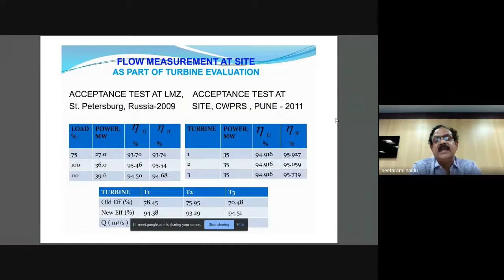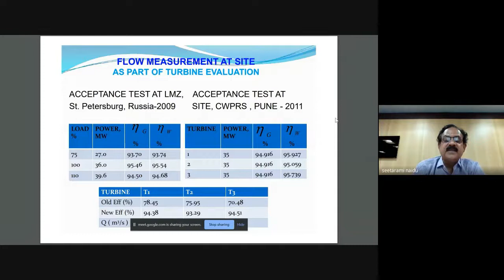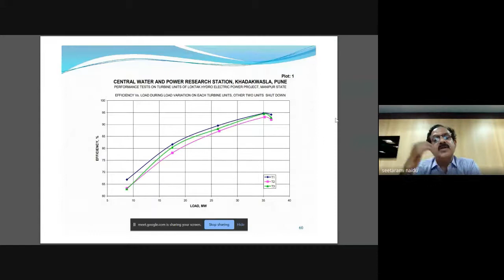In CWPRS we witnessed the acceptance test at site, in 2011 I believe. What they guaranteed is 94.916 for all the units. What we found was an efficiency of 95 odd for all 3. So ultimately, the efficiency has increased from 78 to 94. Just imagine, more than 15% in efficiency. And power generation, from 95 megawatt, could go up by 10% enhancement, up to 126 megawatt.